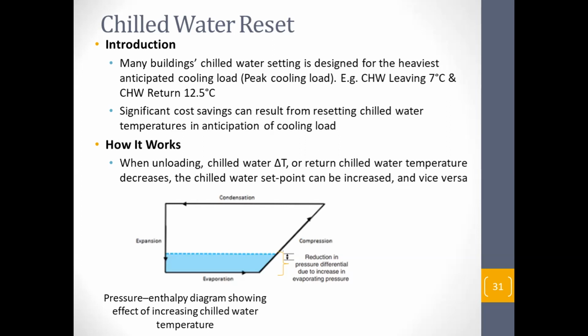When you elevate your chill water, it goes to your air handling unit at a higher temperature as well. If your air handling unit doesn't have excess capacity, it will have difficulty maintaining the temperature inside the space, and your AHU may have to work harder, so the AHU energy cost will go up. When the AHU works harder, your chill water pump has to work harder, so the chill water pump energy cost will go up. Then you have to see the overall benefit, whether it's positive or negative. Don't just increase the temperature without any control. At the same time, there is one more thing to be worried about. One objective of the air handling unit is to remove moisture. When you are giving chill water at a higher temperature, there will be a problem of removing moisture, so inside your premises or the space, the moisture content and RH may be higher.